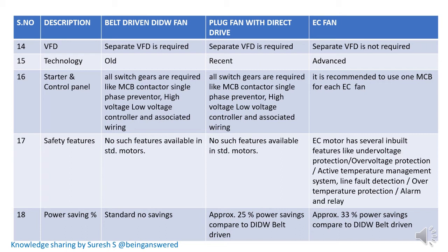Technology wise, EC fan will be the latest advanced technology. For the starter panel and control panel, EC fan needs only one isolator or MCB for each EC fan, because all the controllers are inbuilt and it will control its own. But for plug fan and belt driven DIDW fan, we need all arrangements of MCB, contactor, single phase preventer, high voltage, low voltage controller, and related wiring.